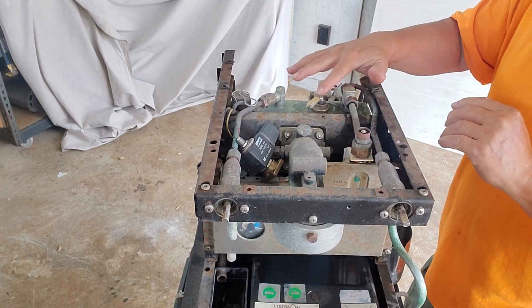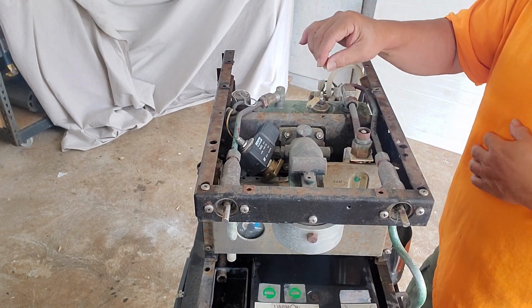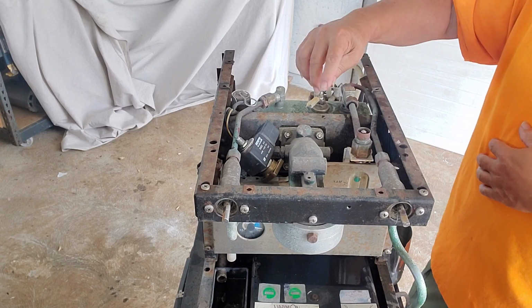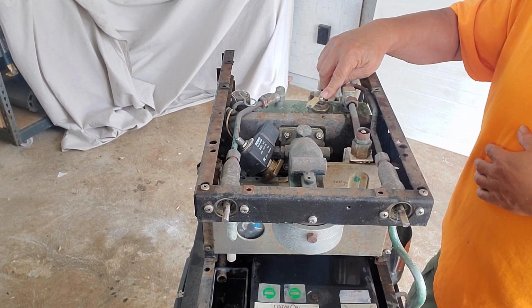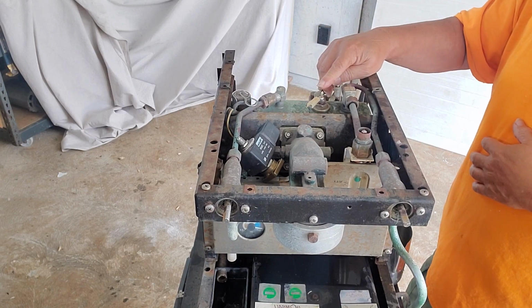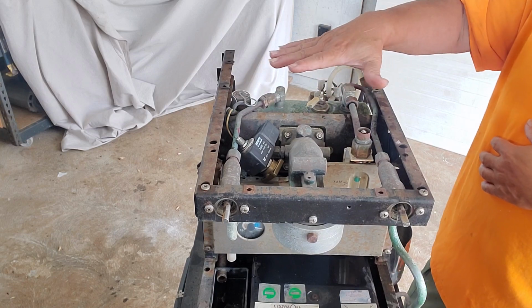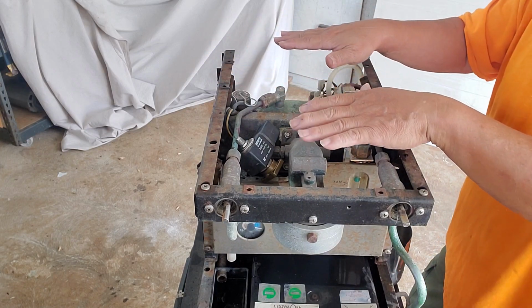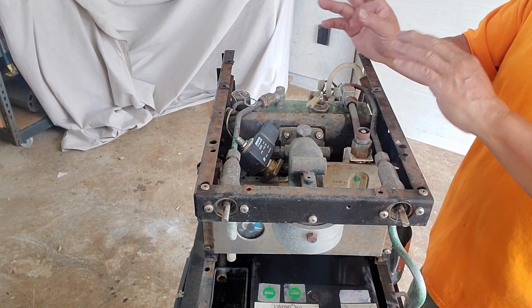And that's where the water probe adjustment is important. As you can see, this position is pretty low. If you go too high, it touches the top of the pan, so you got to watch that. You can't go too high.